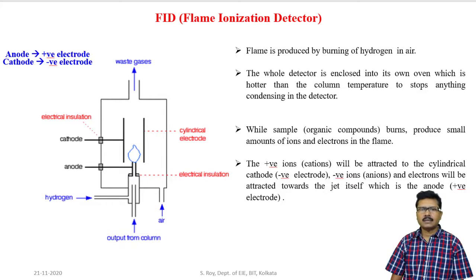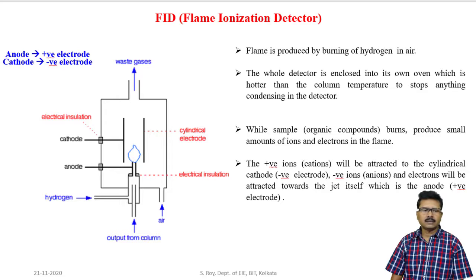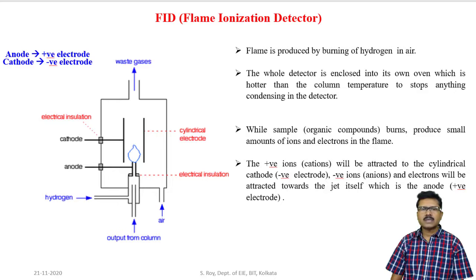The temperature of the detector is higher than the column temperature so that all the samples will be in gaseous form. While there is no organic compound coming from the column, the flame will be produced only due to the presence of hydrogen and air. When a sample of organic compounds enters into the flame ionization detector from the column, that sample will burn and produce small amounts of ions and electrons — both positive ions and negative ions.